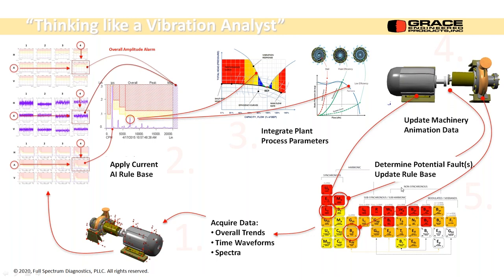Determine potential faults, update the rule base. Here I show that there's an alignment issue, a looseness issue, and a blade passing issue. Those might not be an alarm yet, but they're things we can trend. So instead of just trending overall vibration, we might be able to trend the phase response, which is how the machine's moving, when did it start, how bad is it getting, and so forth. So we have a degree of analysis there.